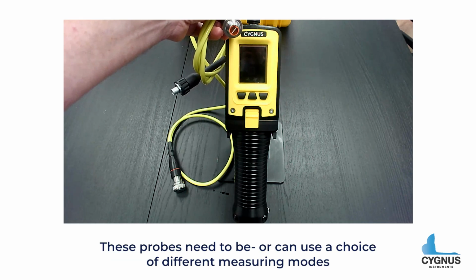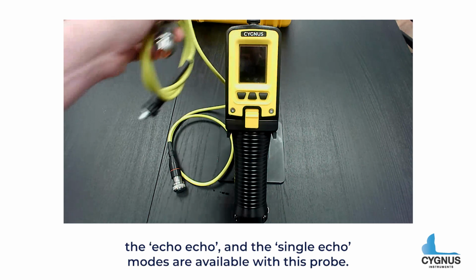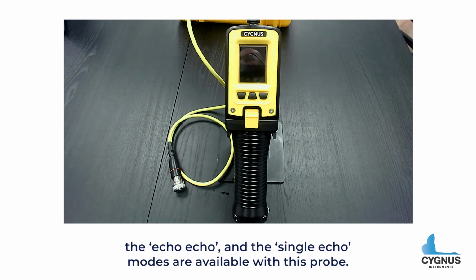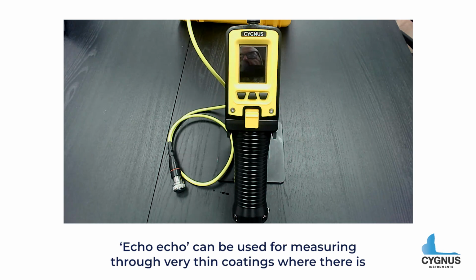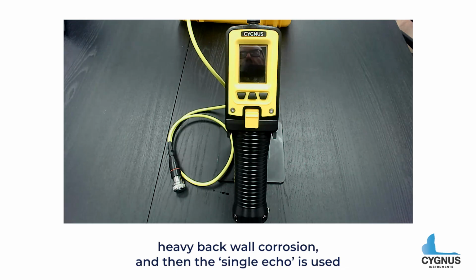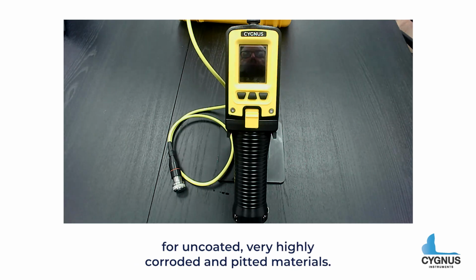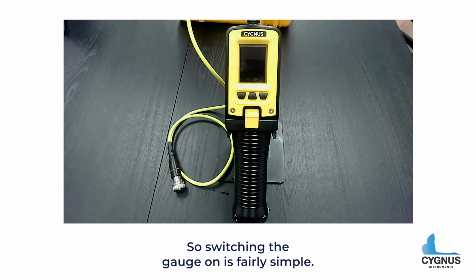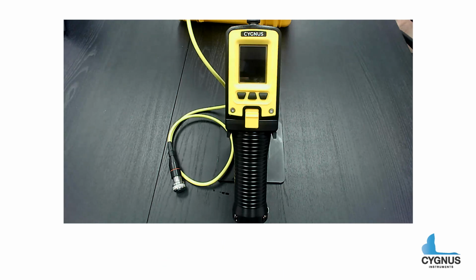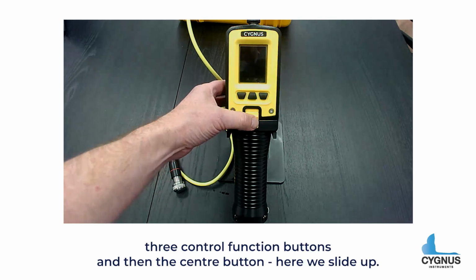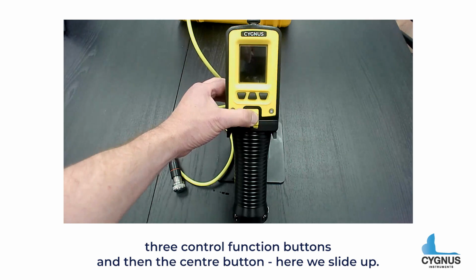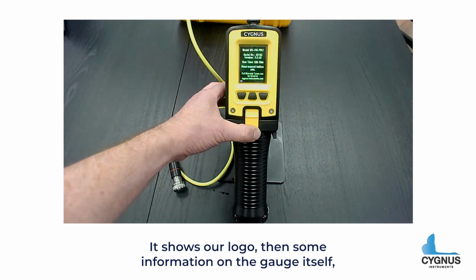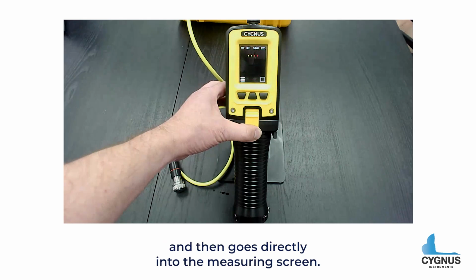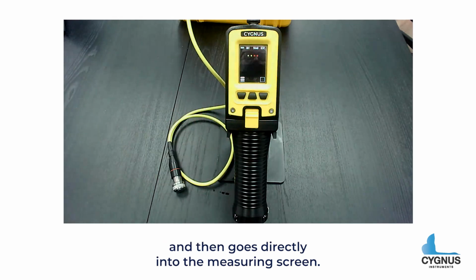These probes can use a choice of different measuring modes. The echo-echo and the single echo modes are available with this probe. Echo echo can be used for measuring through very thin coatings where there is heavy backwall corrosion. And then the single echo is used for uncoated, very highly corroded and pitted materials. So switching the gauge on is fairly simple. We've got all the control buttons here, three control function buttons, and then the center button here we slide up. It shows our logo, then some information on the gauge itself, and then goes directly into the measuring screen.